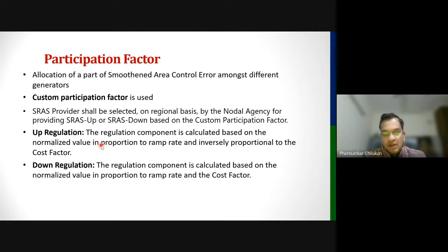For example, if Ramagundam 3 trips, and Ramagundam 1 and 2 have reserve at 5 rupees per kilowatt hour, but there's a power plant in the northern region, Singrauli, at only 2 rupees — the question is whether to increase generation in Ramagundam 1 and 2 or in Singrauli. The best thing is to increase in Singrauli since it's only 2 rupees per kilowatt hour, if there is reserve in that power plant.